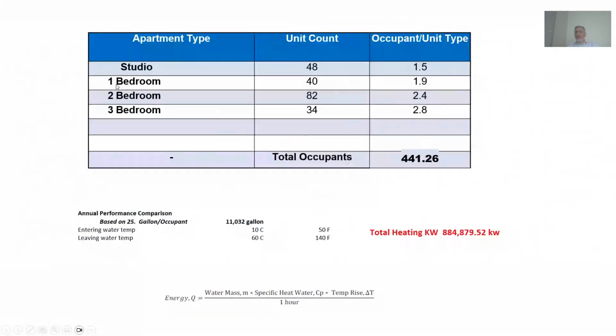So again, moving back to our example, in this apartment building we say there are 48 studio apartments, one bed apartment 40, two bed apartment 82, and three bed 34. Based on our criteria, there are 442 occupants in the building. Based on 25 gallons per occupant, we will need around 11,000 gallons of water for their domestic use. Considering that water is coming in at 10 degrees centigrade and we want to raise it to 60 degrees centigrade, the total energy required for hot water use is 884 kilowatt for 1 year.